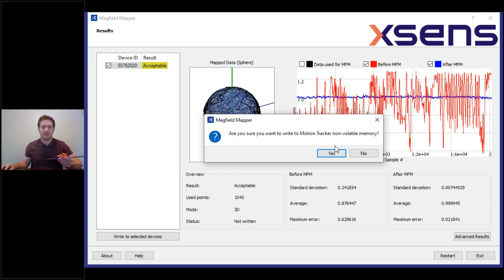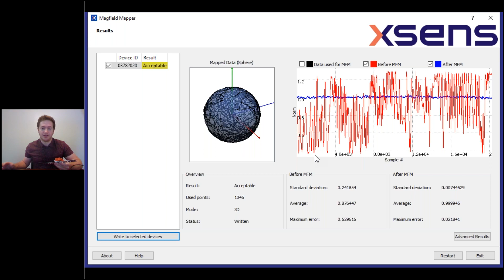Then you're going to go ahead and write to selected devices if you think your calibration looks good. Write to selected device, yes, and it's written to the device. So now this calibration is stored in the internal memory of the MTI. No need to repeat this calibration over and over again, unless of course you change the magnetic environment of the sensor.